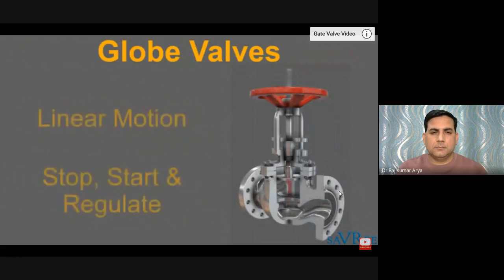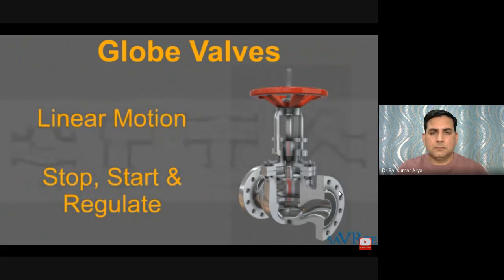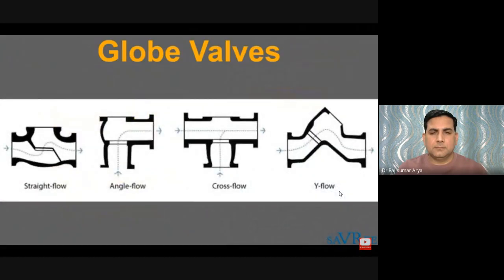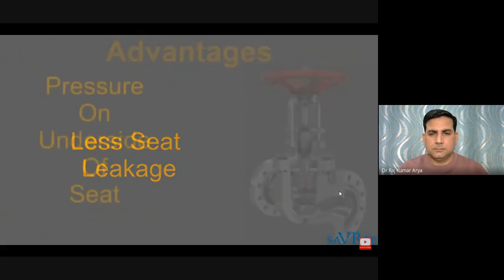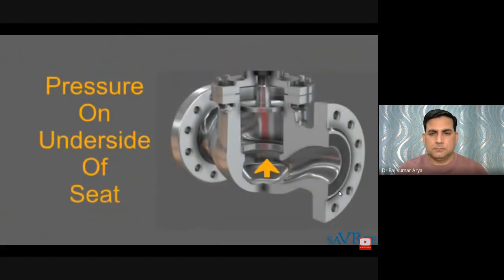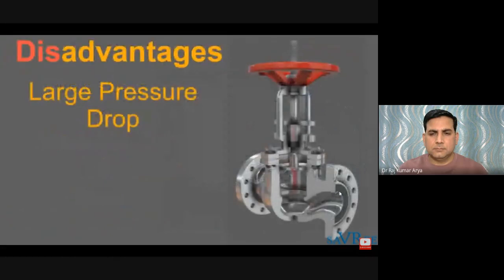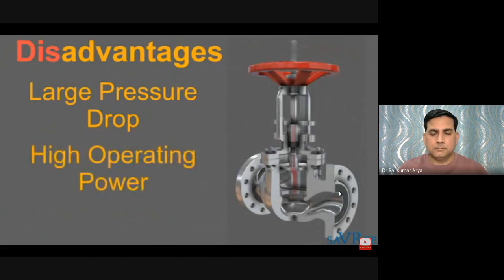The globe valve is a linear motion valve used to stop, start, and regulate fluid flow. There are four main globe valve designs: straight flow, angle flow, cross flow, and Y-flow. Compared to a gate valve, a globe valve generally yields much less seat leakage, because the disc-to-seat contact is more at right angles, which permits the closing force to tightly seat the disc. Globe valves are almost always installed with system pressure on the underside of the valve seat. The largest disadvantage is a relatively large pressure drop across the valve, and large globe valves require considerable power to operate and are especially noisy in high-pressure applications.